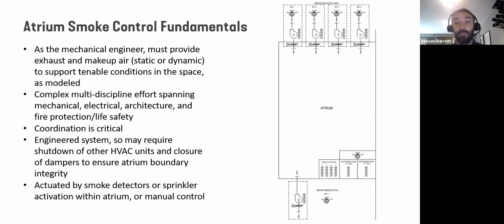And unlike these other systems where I gave you that poll question to say, hey, does a sprinkler activate or does a sprinkler shut down an HVAC unit? Well, within the atrium, the smoke detectors, sprinkler water flow, and manual control at the firefighter's smoke control panel, all of those will activate the smoke control system and initiate that whole sequence of events, possibly shutting down unrelated HVAC units and activating. You can see here on the screen, I've got just a snip of 4 roof-mounted smoke exhaust fans and a makeup air fan providing air to the base of the atrium.